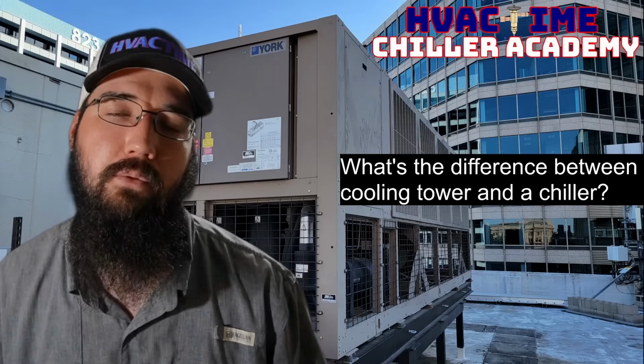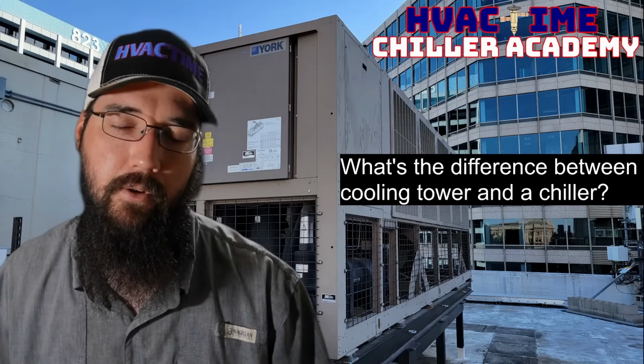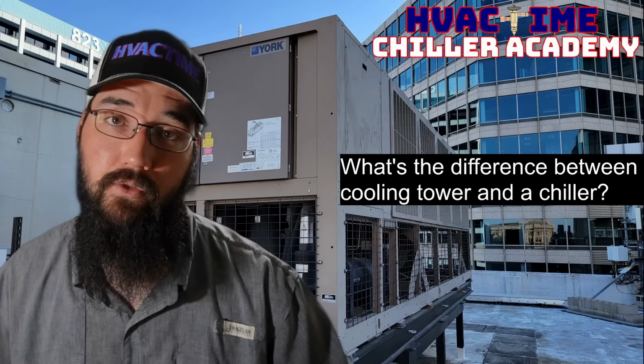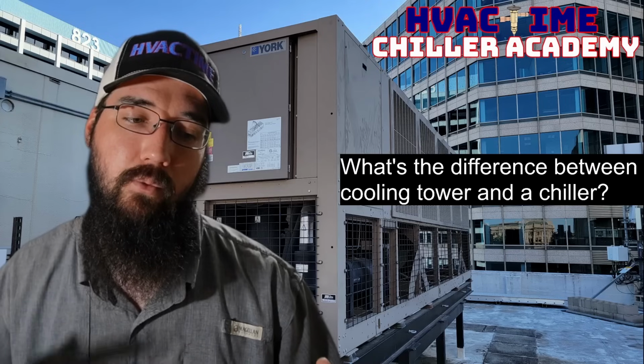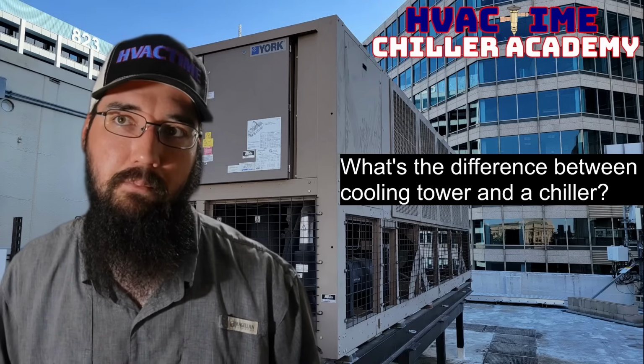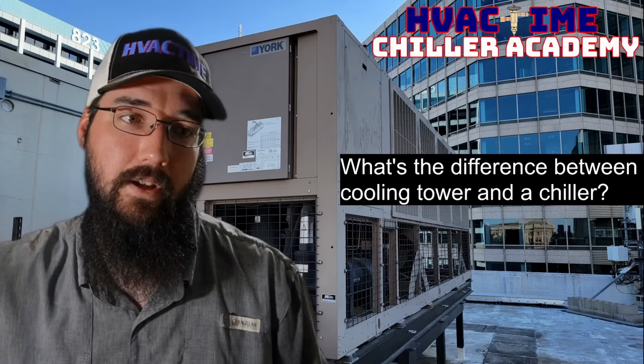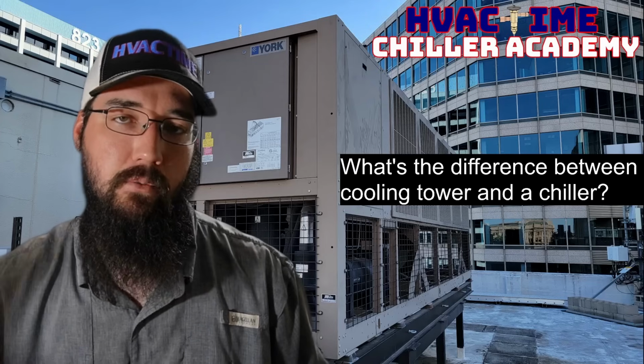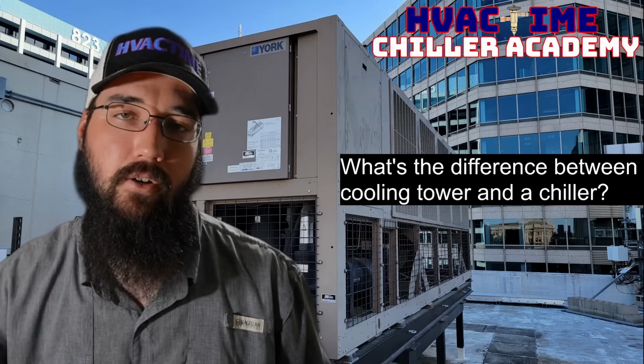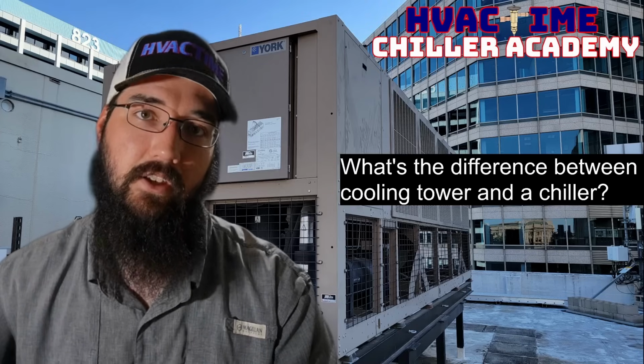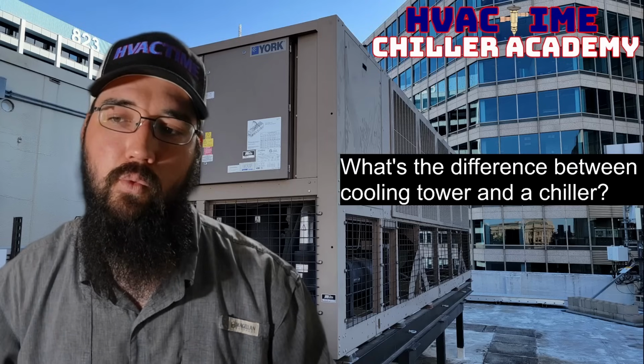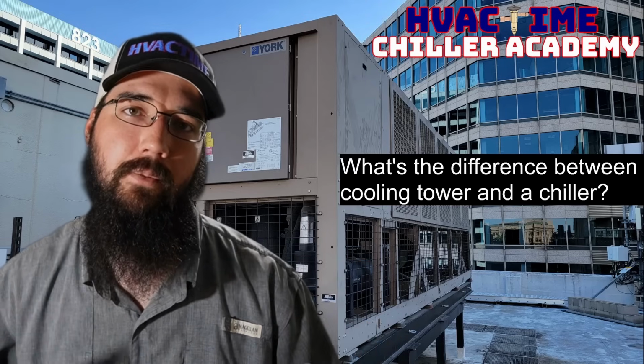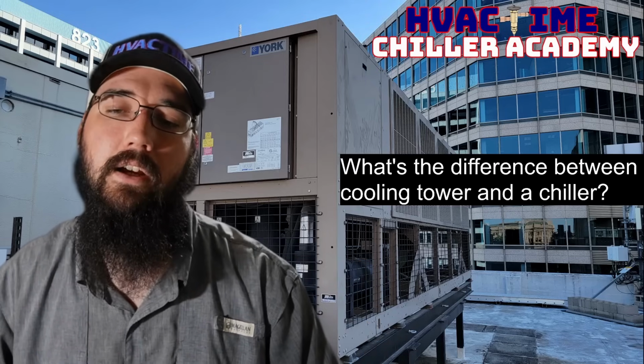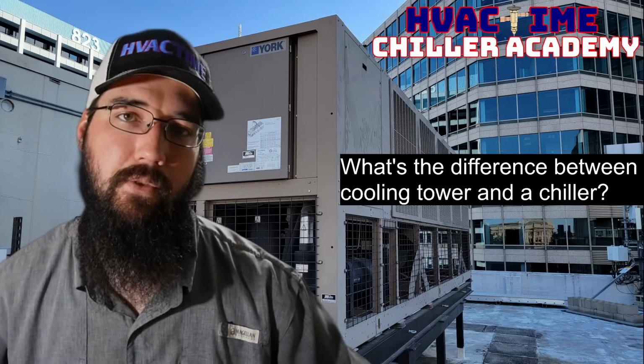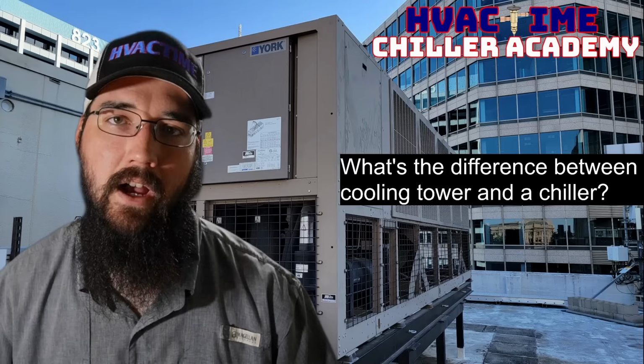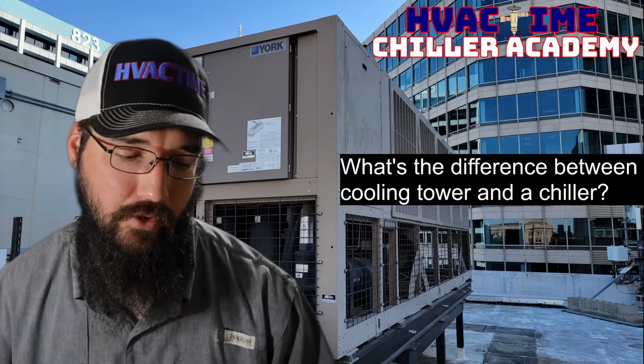So there's usually not any refrigerant under a basic application. There's not refrigerant flowing through a tower. That would be a remote condenser. And there are those. So we do have things like remote condensers, where we have a system similar to a self-contained where all the basic components are inside, but the condenser has been moved to an outside location somewhere. And we have refrigerant piping running out to that remote condenser. And it is actual refrigerant and little air-cooled coils sitting out there with condenser fans. Those also exist, but those are not considered towers. They're remote condensers. So when we say a cooling tower, we're referring to something that is processing condenser water in terms of a chiller. It gets far more specialty applications from there, as we can use it in various ways. And the style of tower then plays a part in what all it can do in its own context.